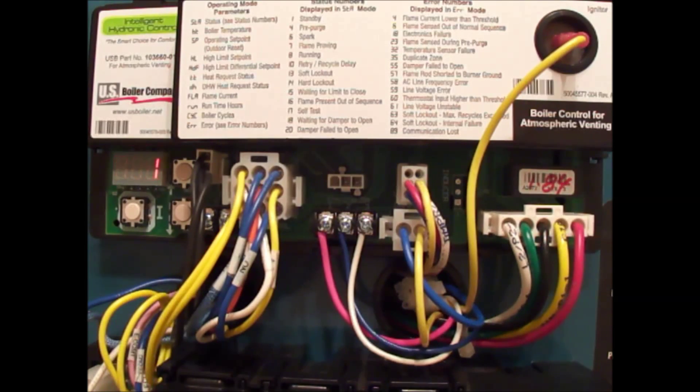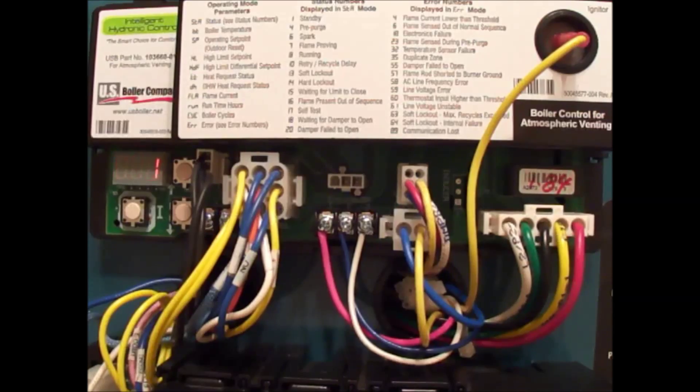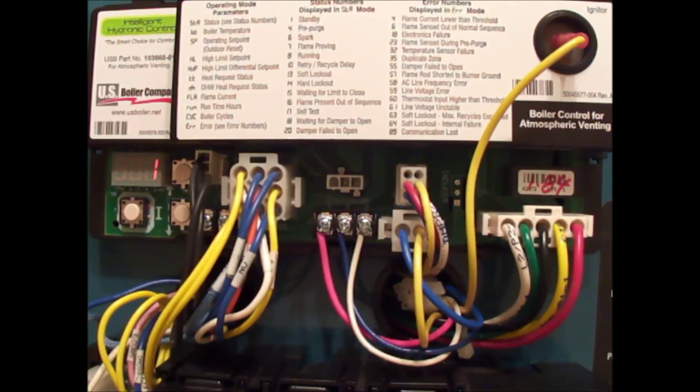This is a new code that came about September 1st of 2012. We have to use residual heat first—turn the pump on, let it run and drop the water temperature below 140, then fire the boiler. If the boiler is less than 140, it can fire up as soon as we check the water temperature and make sure it's not above 140.